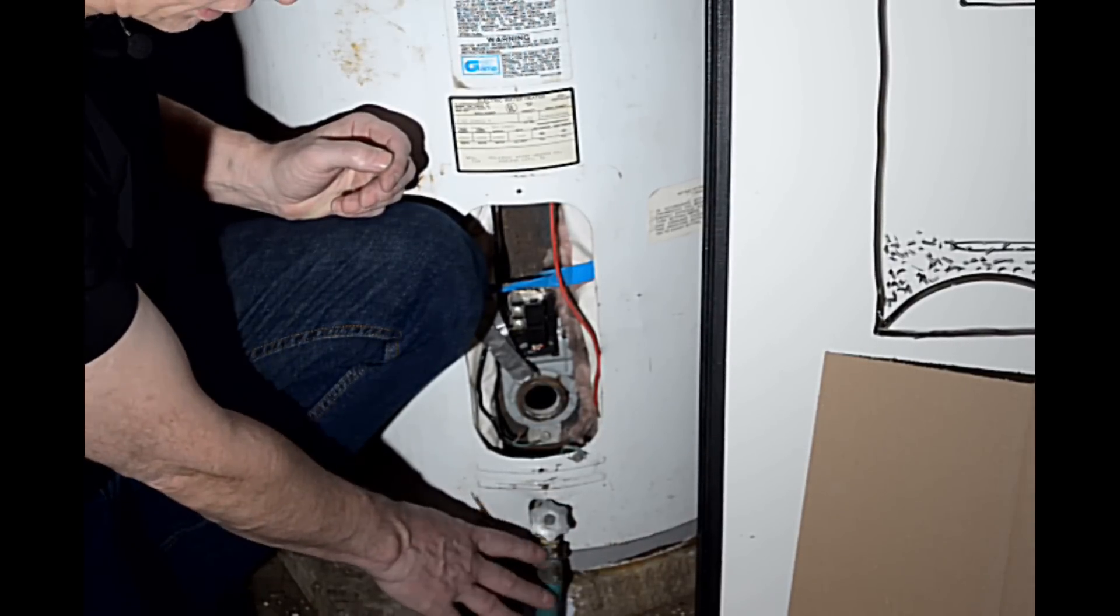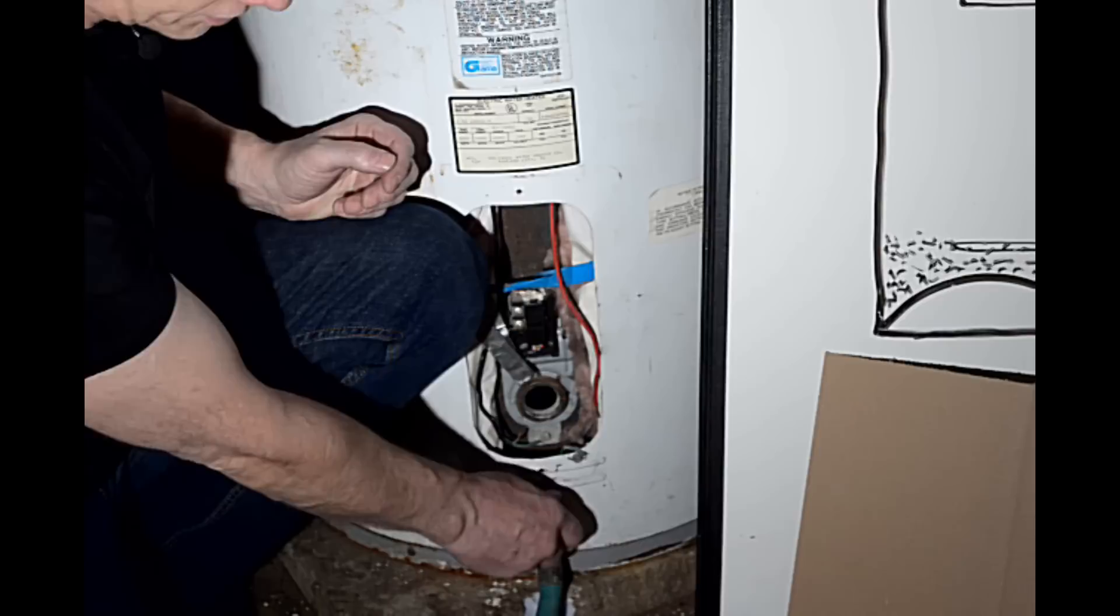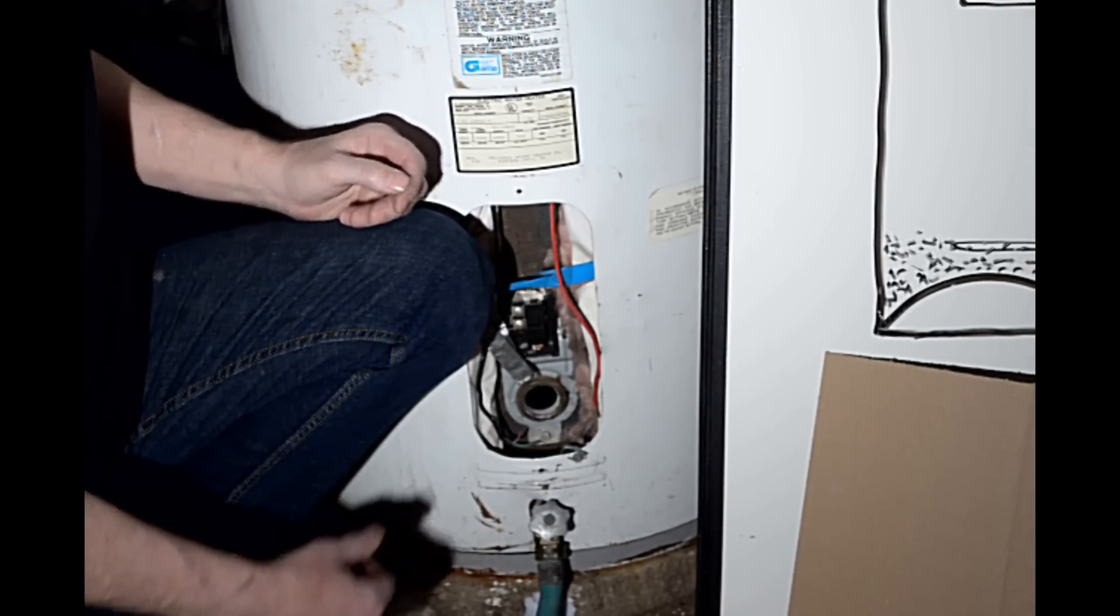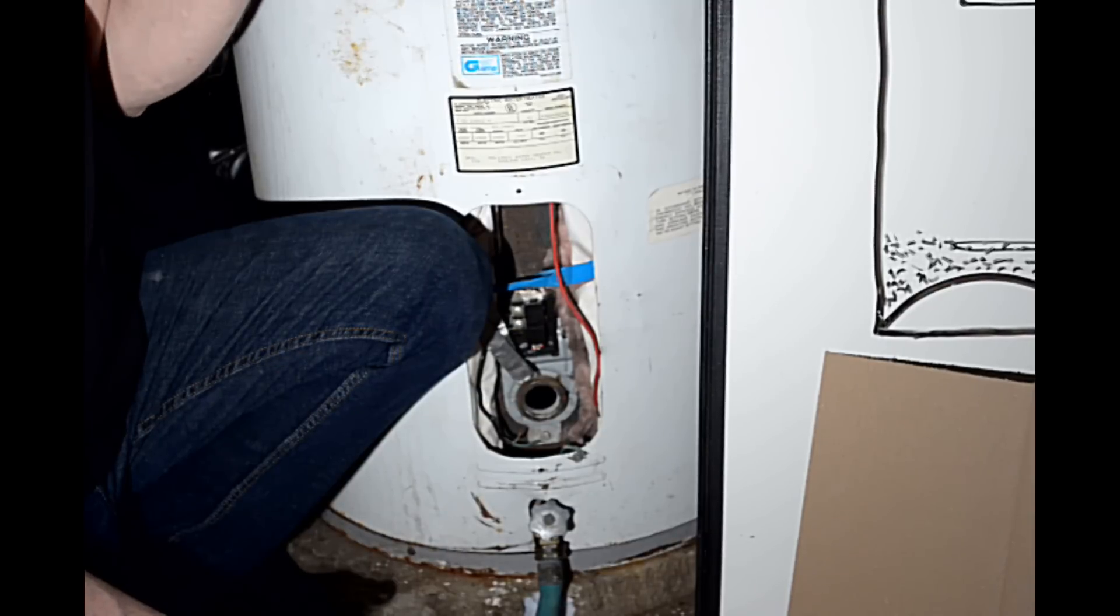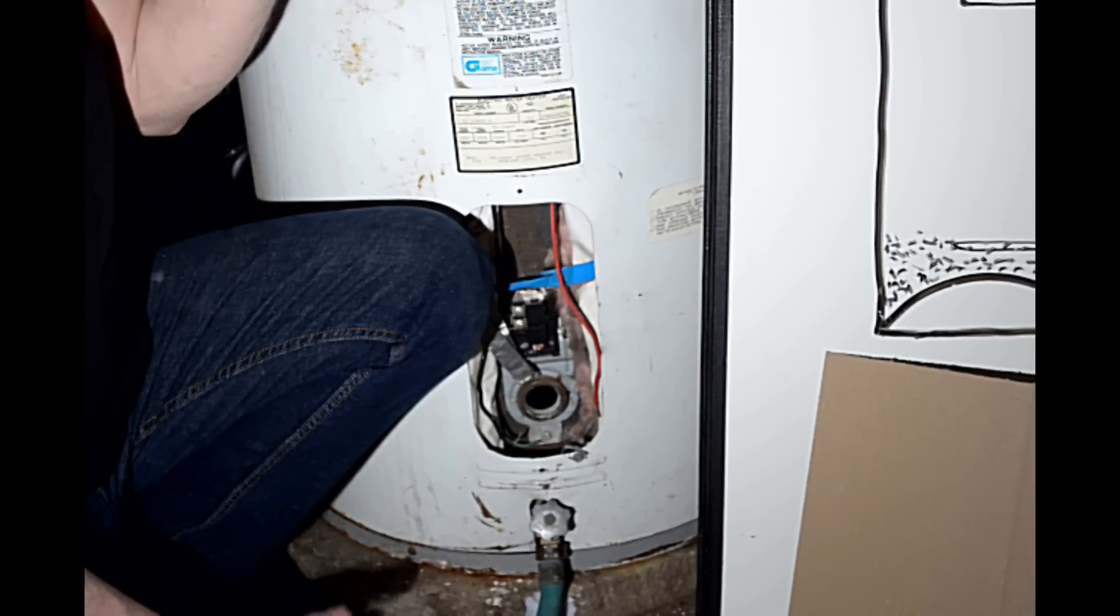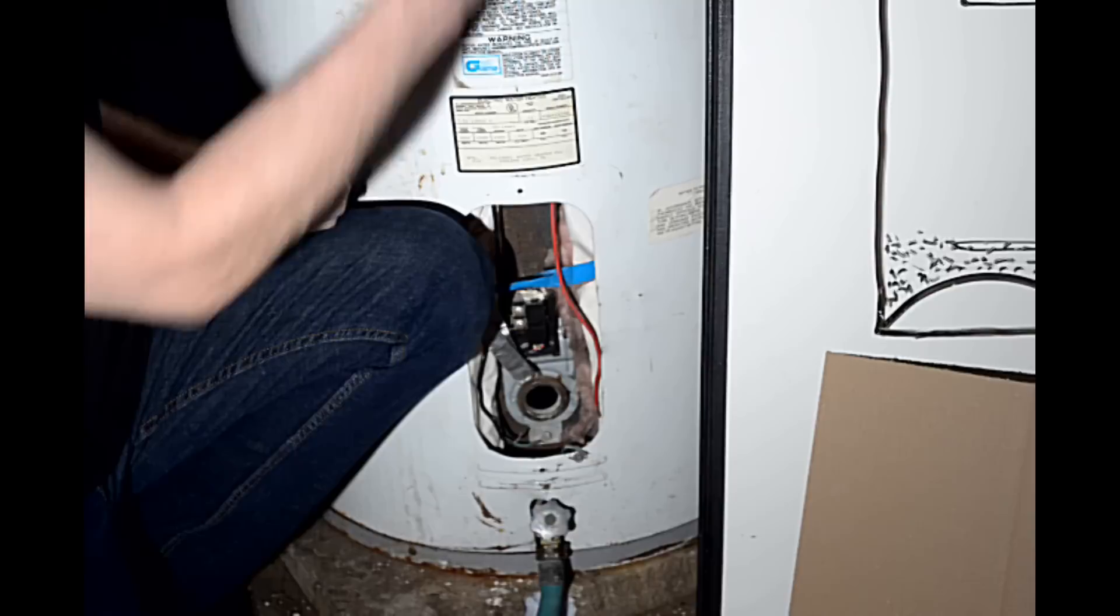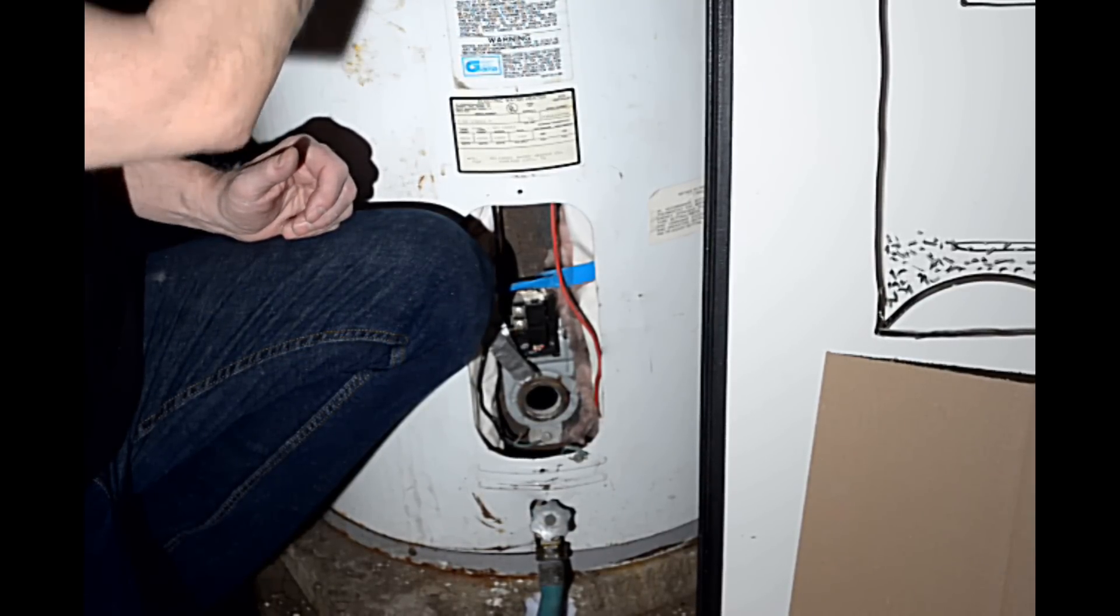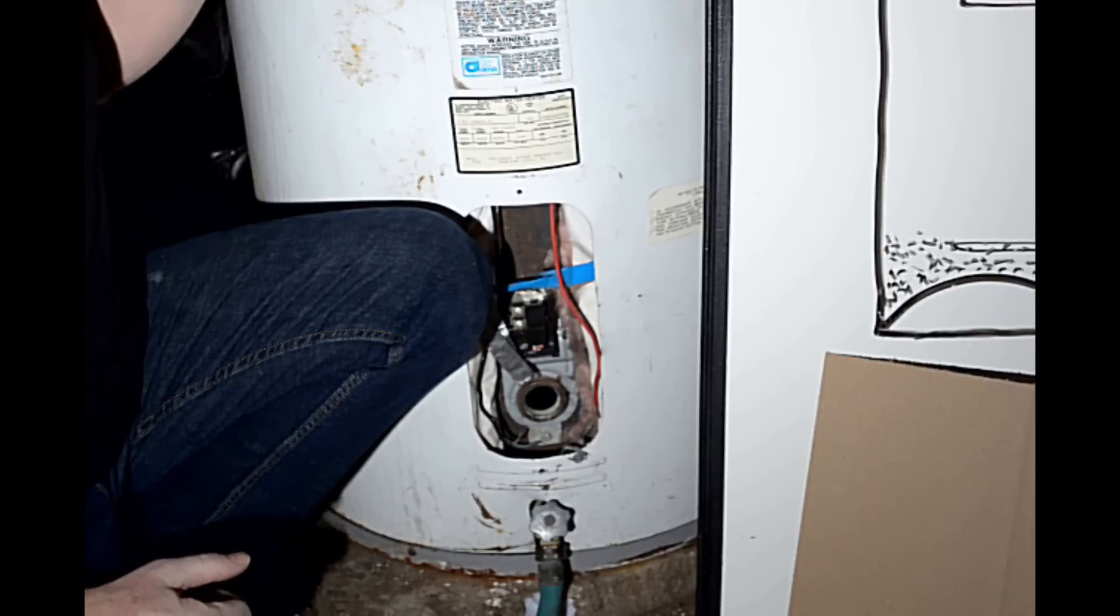Go ahead and start, turn on the valve to start draining it. And then you may want to open up a valve to allow air to come into the top of the tank until the water level comes down below the first element.